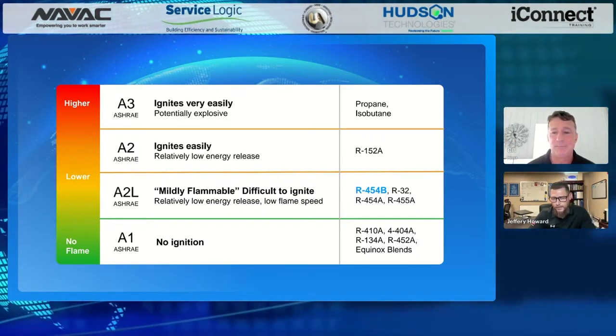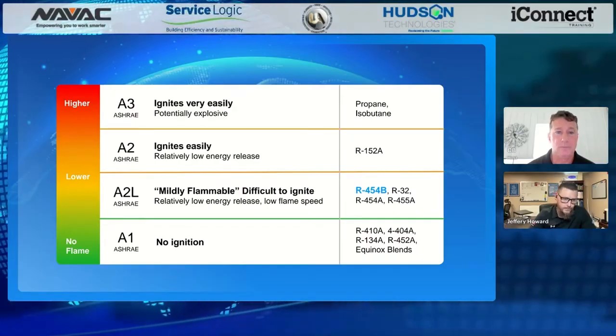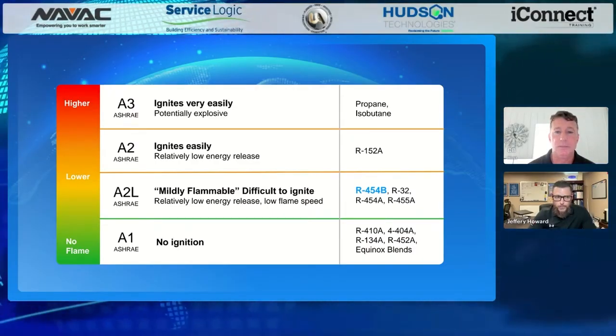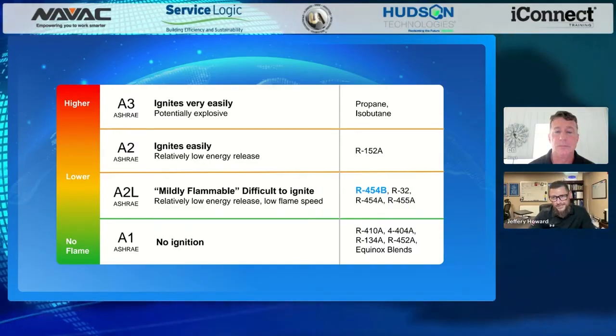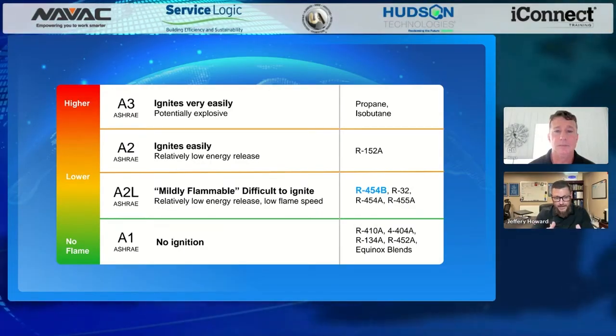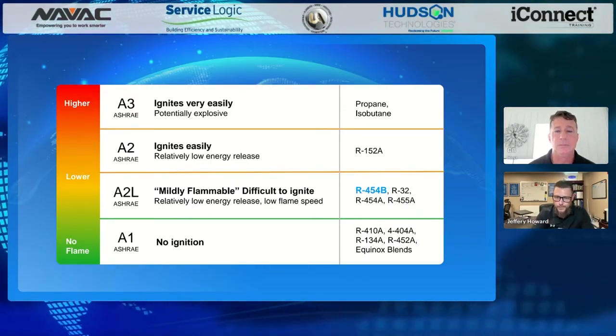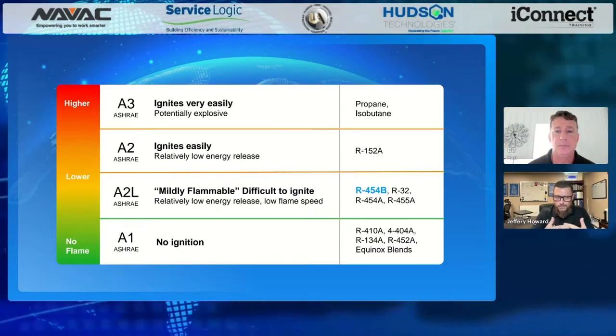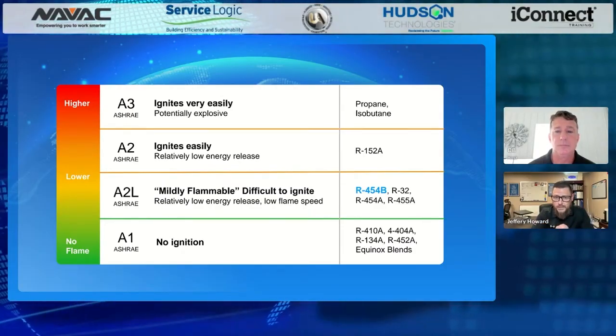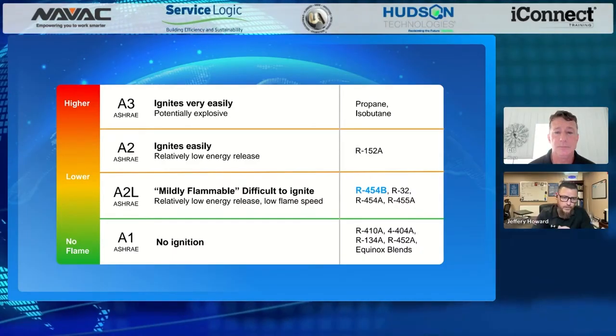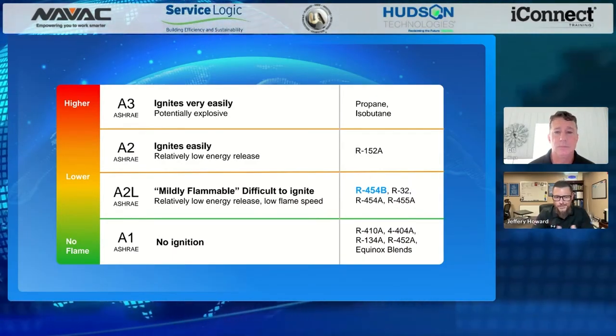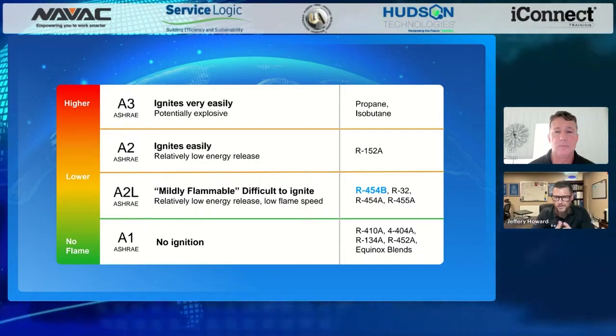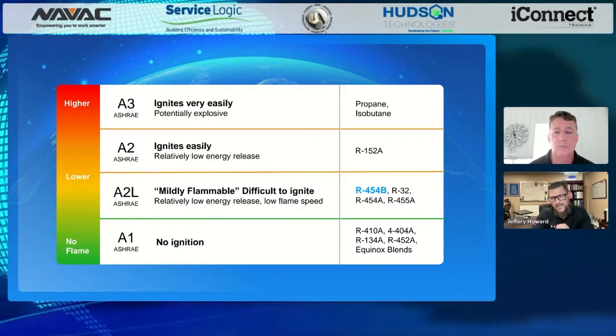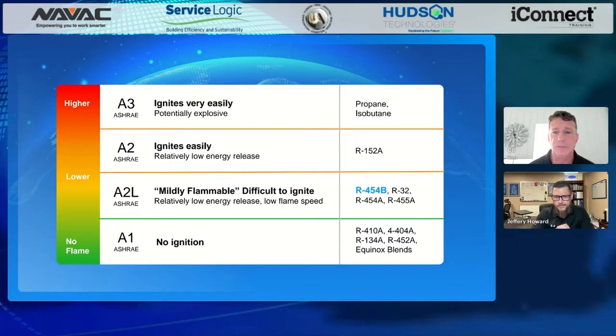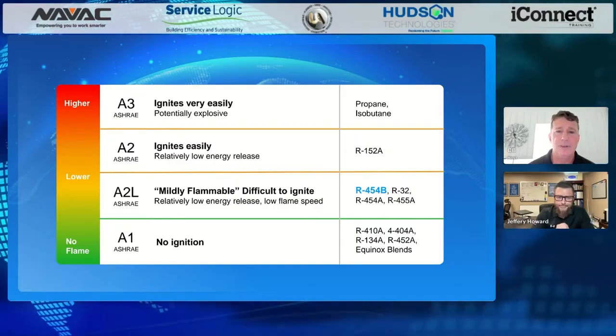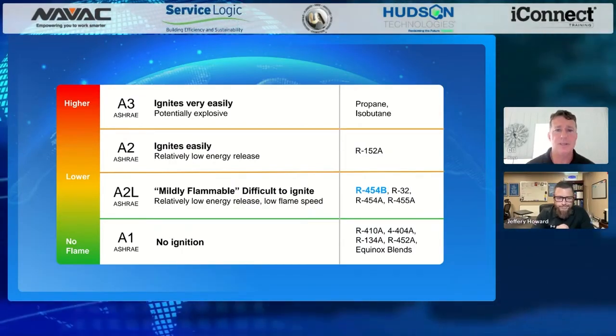With our Puron Advance compared to Puron, we're looking at roughly, again we talk about change, that pressure we're used to seeing with Puron is, with Puron Advance, within about 7%. So it's not far off. If you look at that on your gauges, the pressure is anywhere between 10 to 40, or 10 to 50 psi on your scales. Very similar. It's not a significant transition for people.